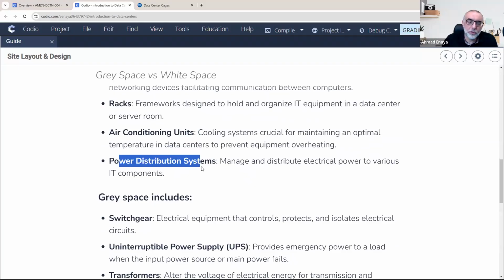The racks and servers should be powered, which means some components of the power system are used to connect to the power distribution units, PDUs as we call them. So the power distribution system must be in the same server room, the white space. The rest of the power system - the switchgear, generators, UPS - is all in the gray space.